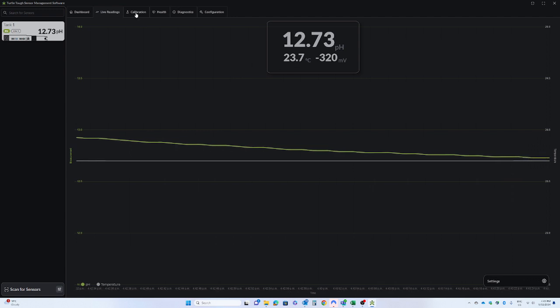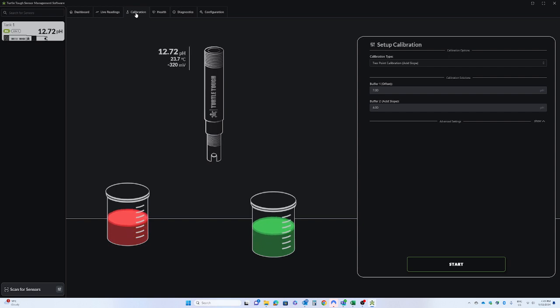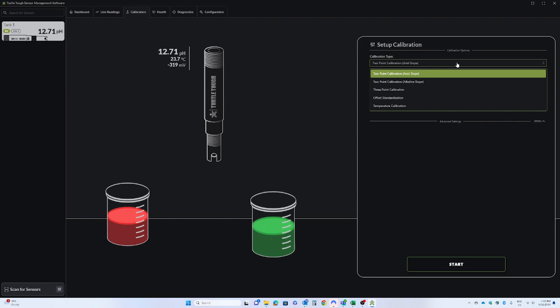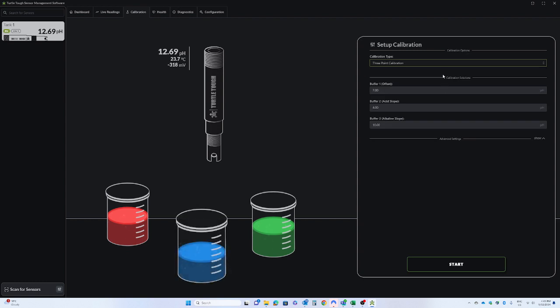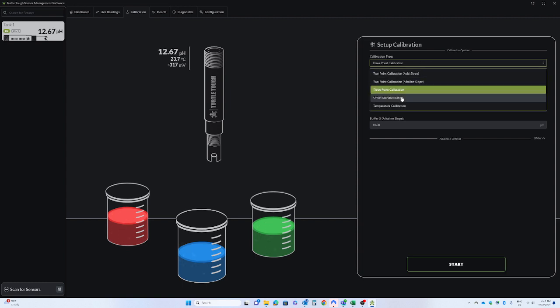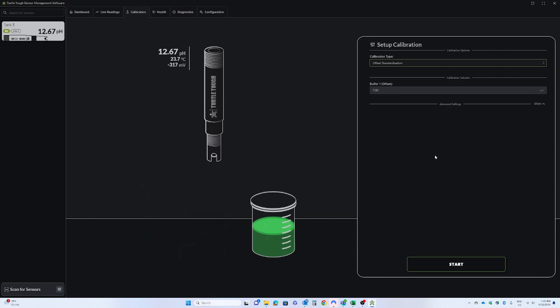The next window, and arguably one of the most important, is the calibration feature. The calibration window allows us to do a wide variety of calibrations, including a 2-point calibration for both the acid and the alkaline slope. Additionally, you can do a 3-point calibration, and it's important to note that all sensors come from the factory with an inbuilt 3-point calibration in place. You can also do an offset calibration. So if you've obtained an accurate grab sample from your process, and you wish to standardize the sensor against that result, you can use this function here.